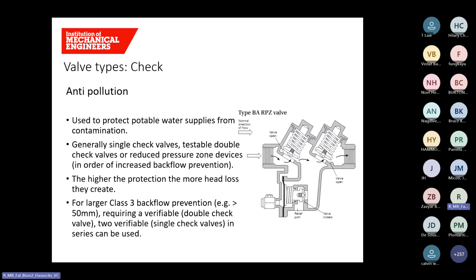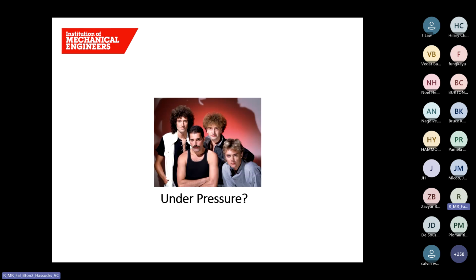Generally, the higher the level of protection, the greater the head loss that occurs across the valve. So that's just something to bear in mind. These reduced pressure zone devices tend to get quite expensive the larger they are. So for applications above 50 millimeters, we tend to use conventional check valves in series with the bleed point in between. Under pressure, not to worry.